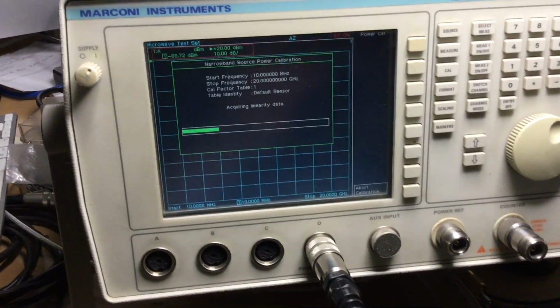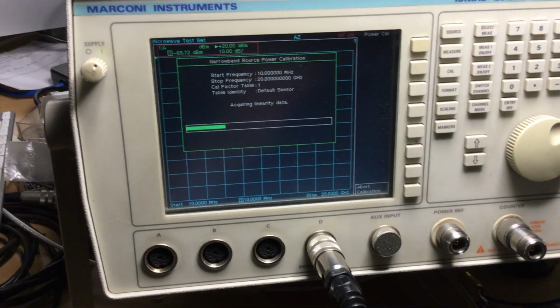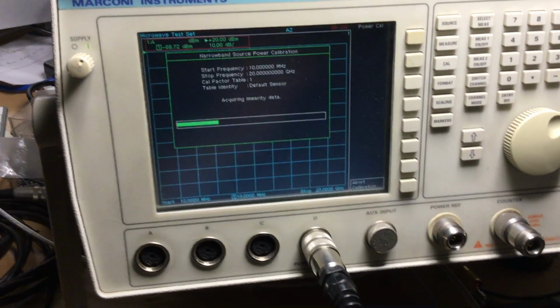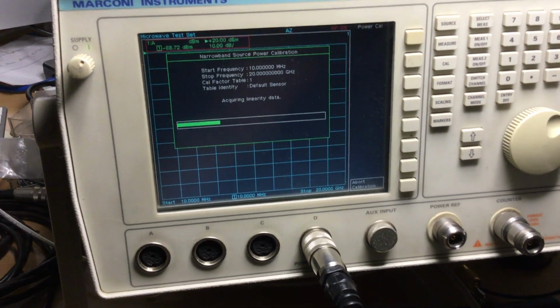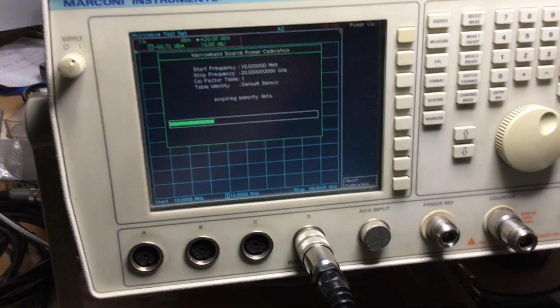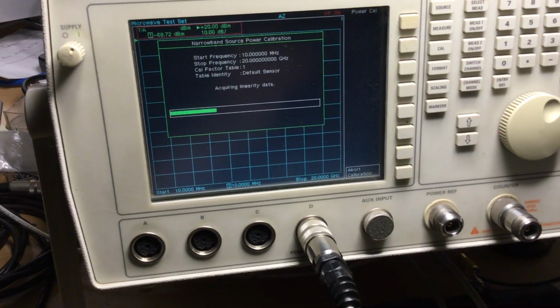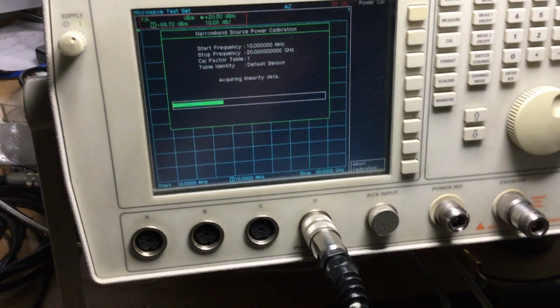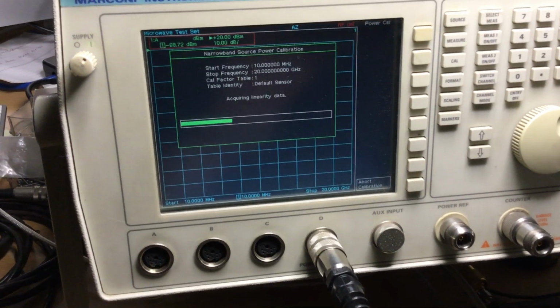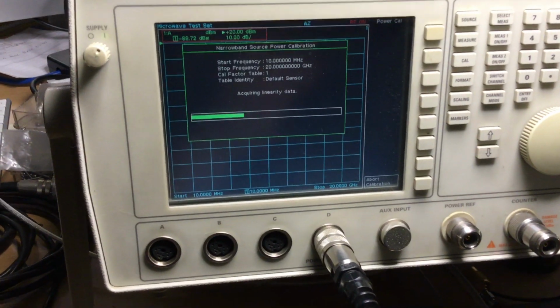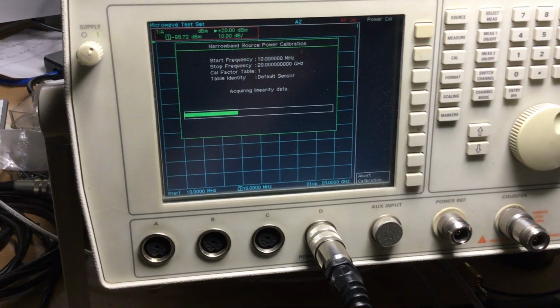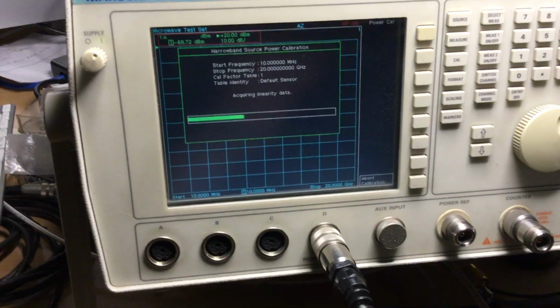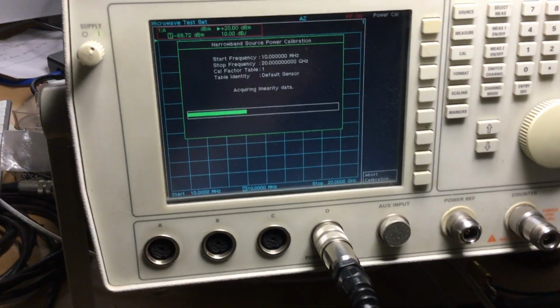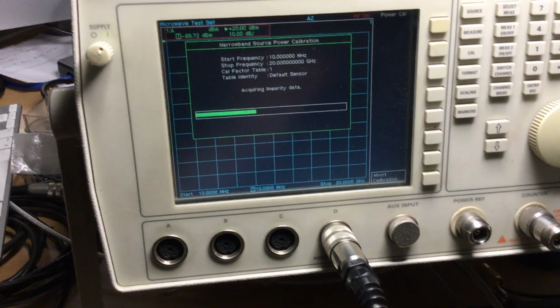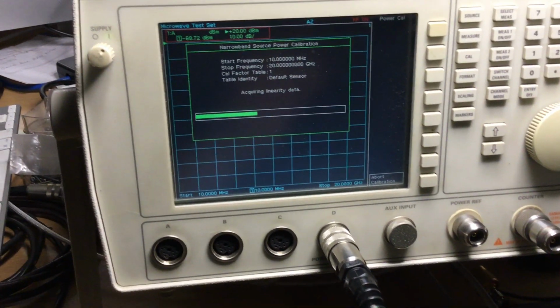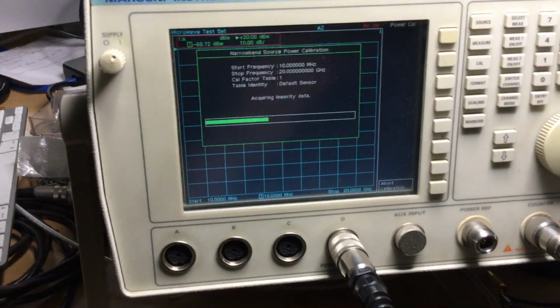So take photographs, using your phone or your iPad or whatever, of where cables and plugs connect to. This particular test set does have a lot of plugs in it around the YIG assembly, the microwave chassis assembly, that are the same pinouts and shape, so you can plug them in the wrong socket when you reassemble. So my advice there is to put a coloured label or a sticker, or write on them as I did, PLA, PLB, PLC, etc. So when you reassemble the cable or the plug back onto the module, on the sockets, on the boards and the modules, you know where they go.